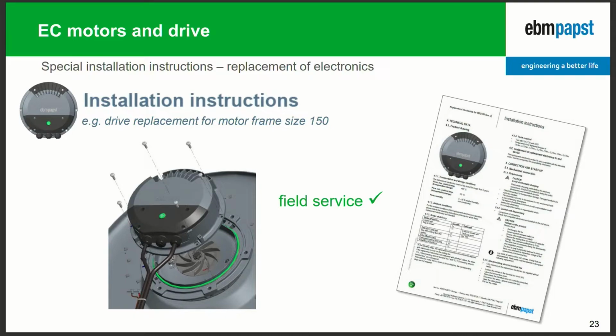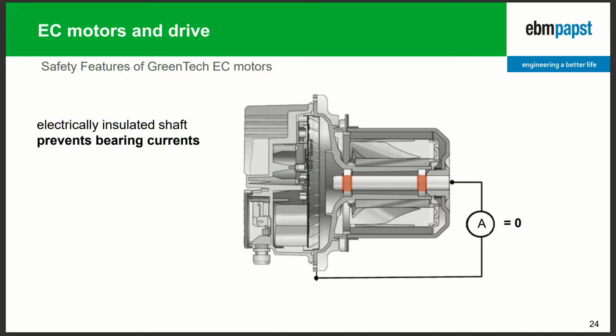Even though the electronic is inside or in a part of the motor, it can be replaced on site in case of damage. So this is also something that is remarkable. Then there's another point. When you have fast switching elements like inverters, VSDs, drives, like our commutation electronic, which is more or less the same functionality as a VFD, you create a voltage difference between the stator and the rotor. This is the physics behind it, and this voltage can create a current through the bearings.